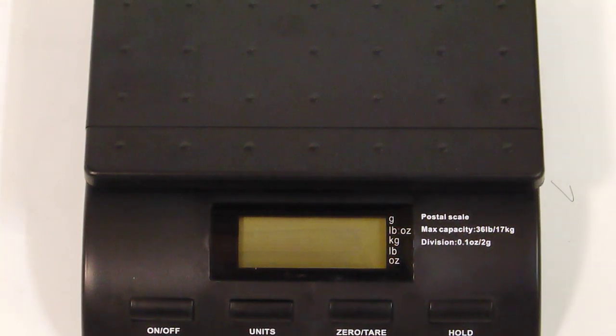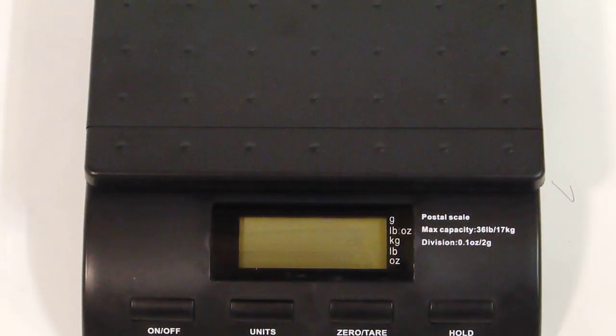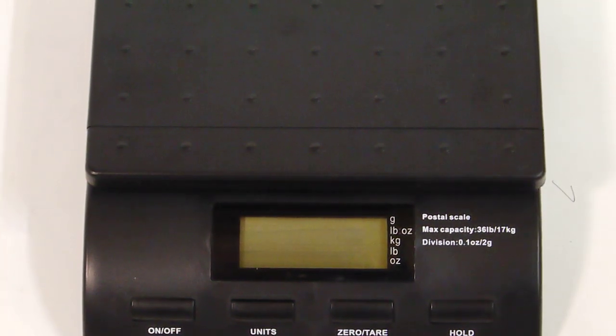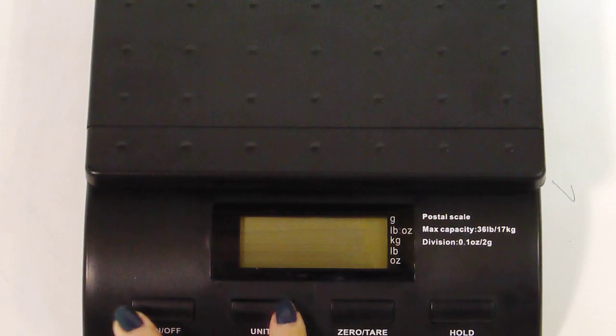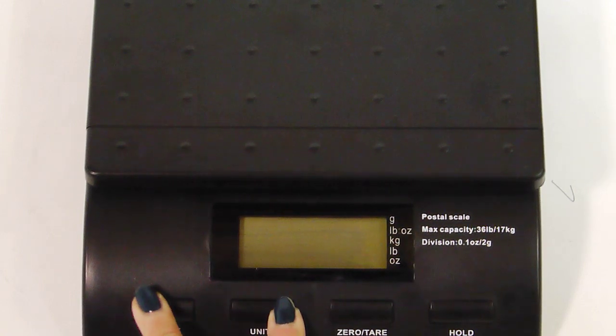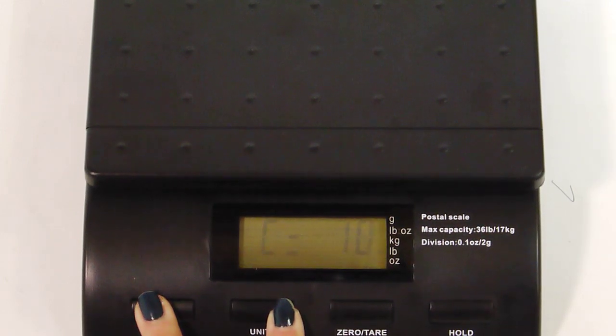This video shows you how to calibrate the SC postal scale. First, press and hold the unit key and press the on/off key.